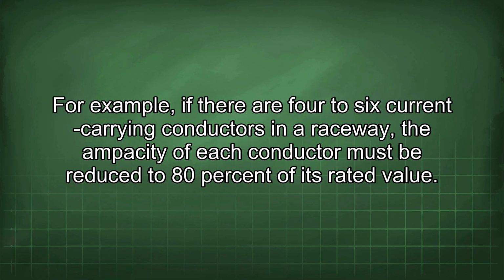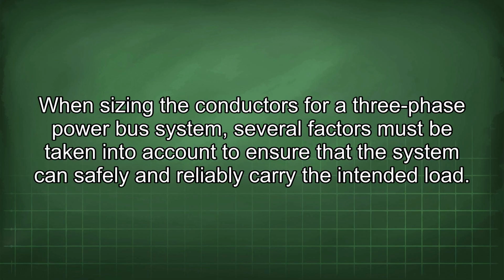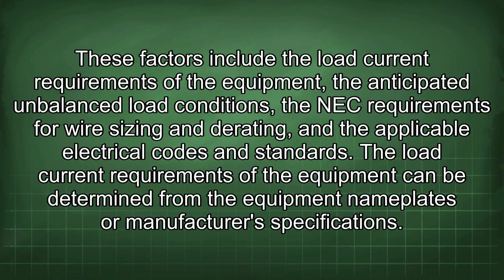For example, if there are 4 to 6 current-carrying conductors in a raceway, the ampacity of each conductor must be reduced to 80% of its rated value. When sizing the conductors for a three-phase power bus system, several factors must be taken into account to ensure that the system can safely and reliably carry the intended load. These factors include the load current requirements of the equipment, the anticipated unbalanced load conditions, the NEC requirements for wire sizing and derating, and the applicable electrical codes and standards.